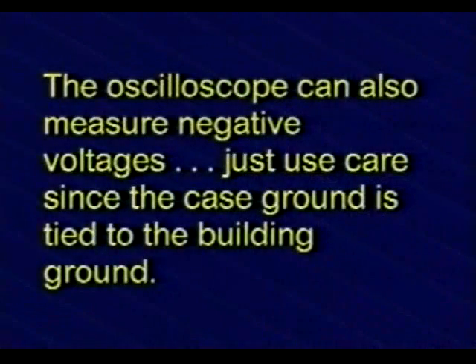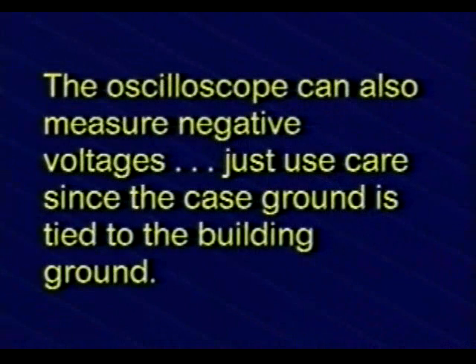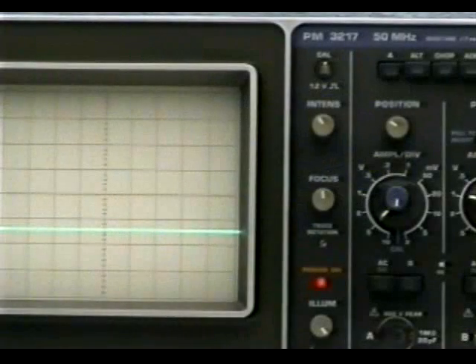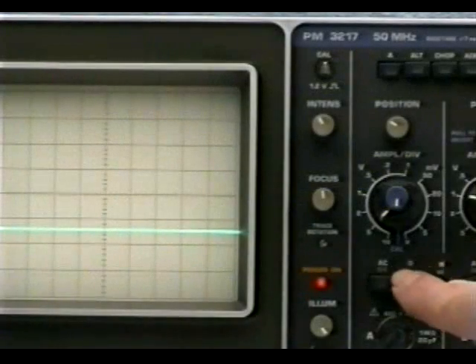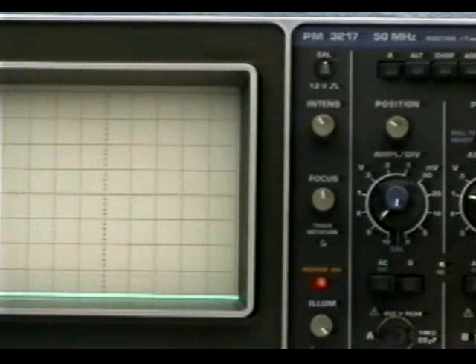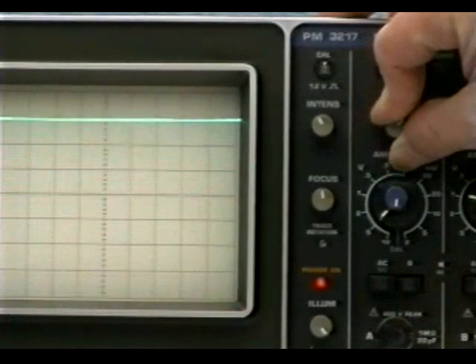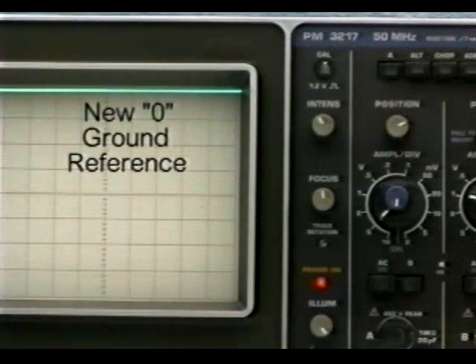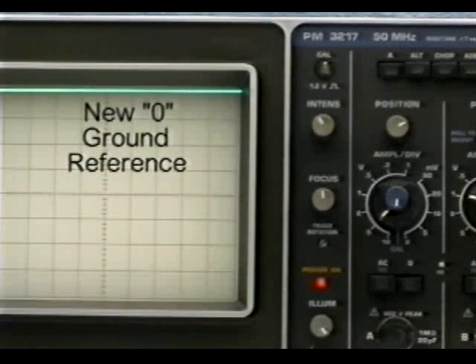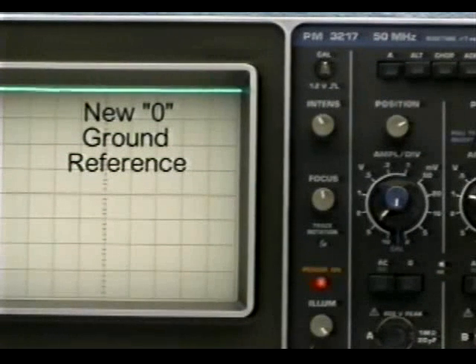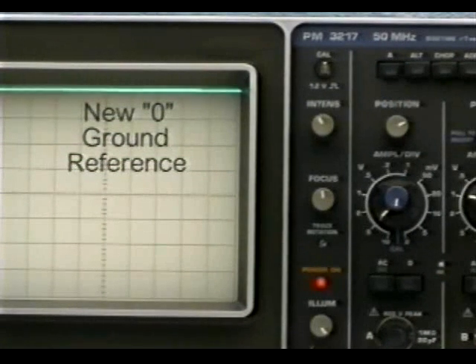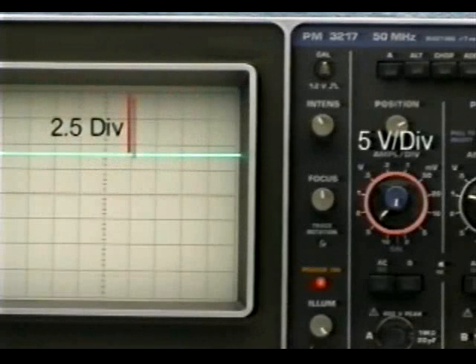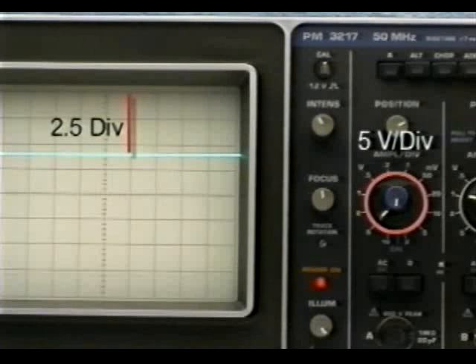The oscilloscope can also measure negative voltages. Just use care because the case ground of the instrument is tied to the building ground. To measure negative DC voltages, we'll need to move our ground reference trace to the top of the graticule instead of the bottom.